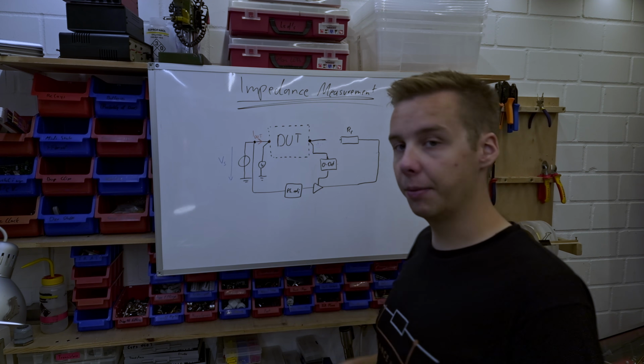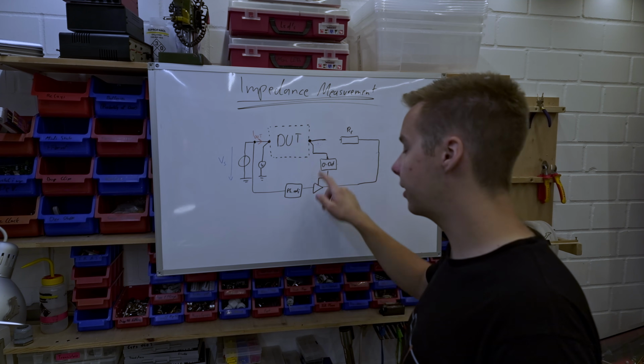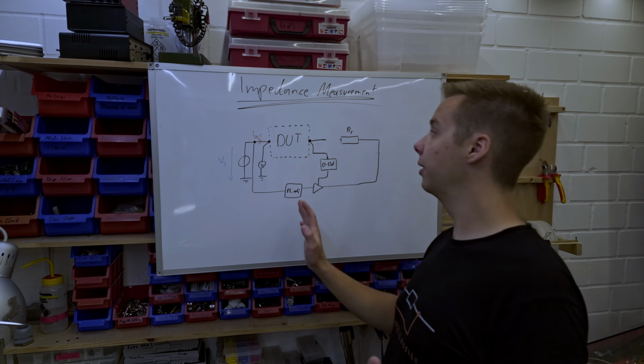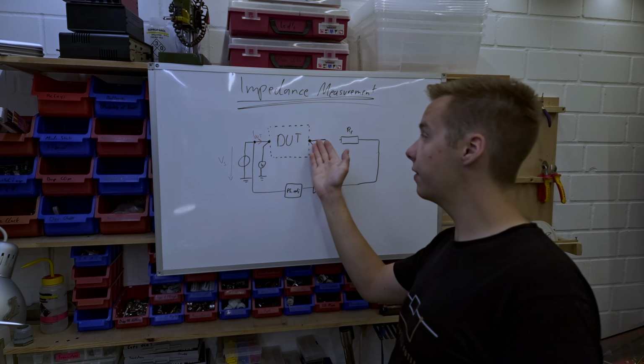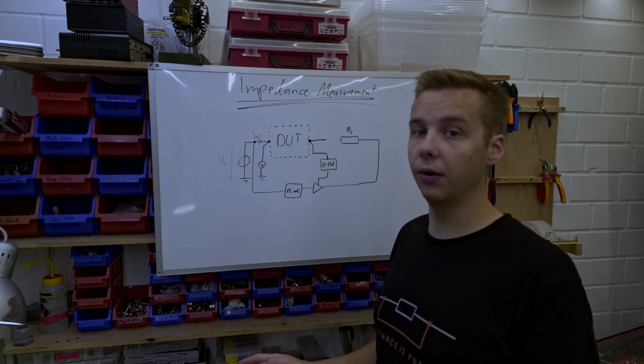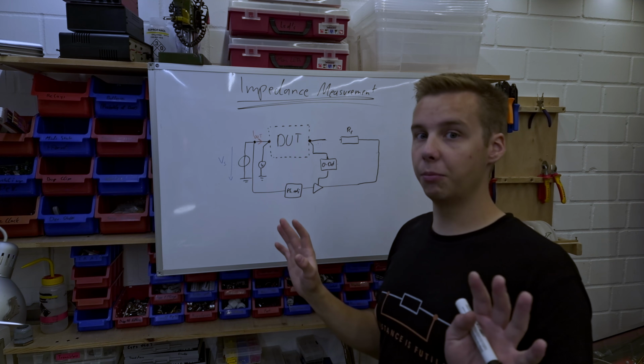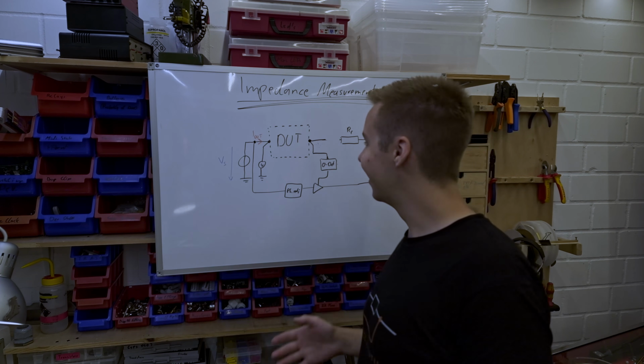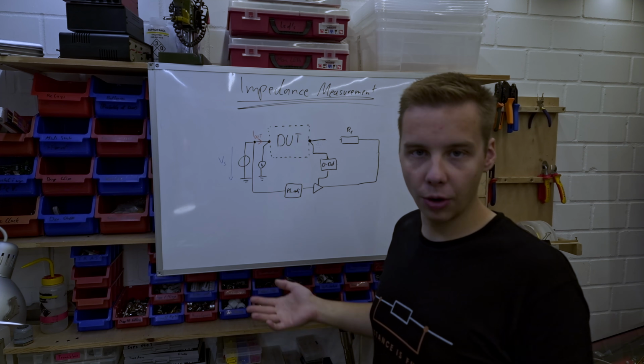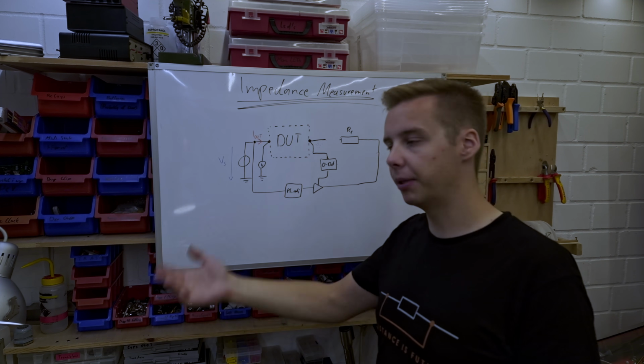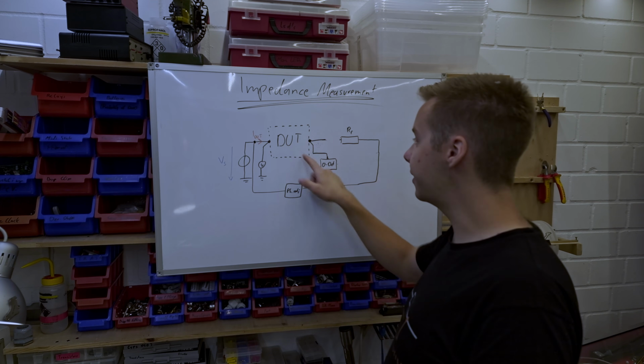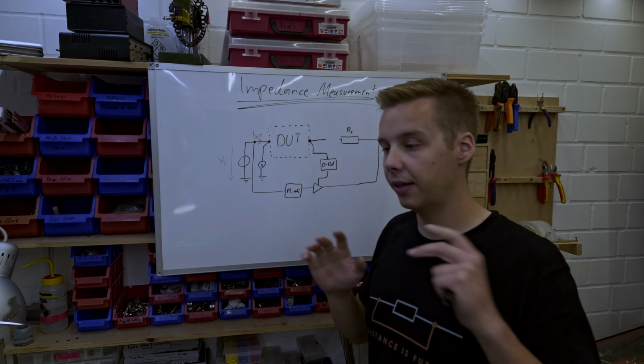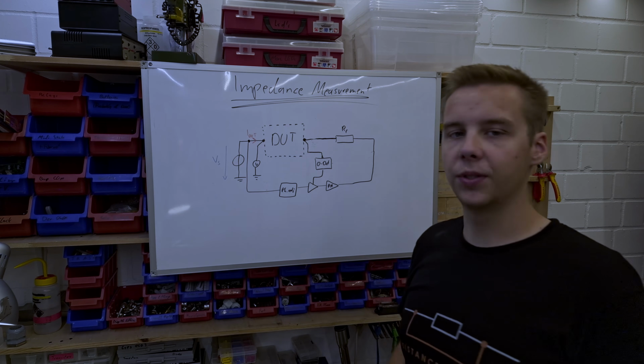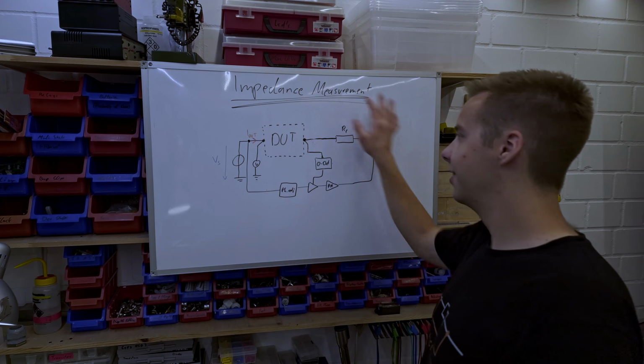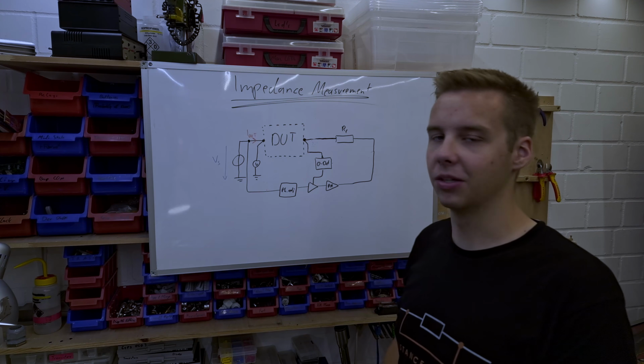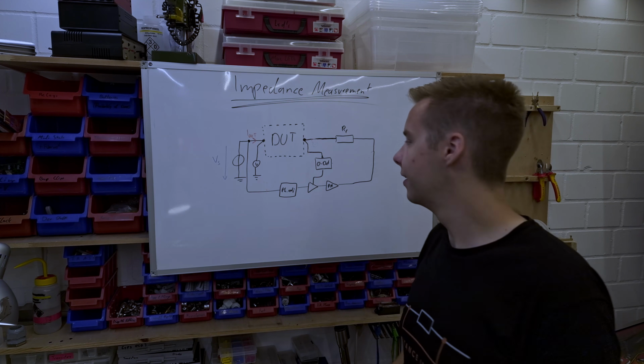At that point, there's a separate detector in the null detector that says, hey, something is going wrong. We've been at a voltage other than 0 at this point here for far too long. I don't know what it is, but the bridge is unbalanced. And something is wrong, we're in an error condition, better tell the user. And in this situation, it tells, hey, bridge is unbalanced. Sorry about the slight change in drawn image. I had to re-record a section because my camera app is going a bit nuts.